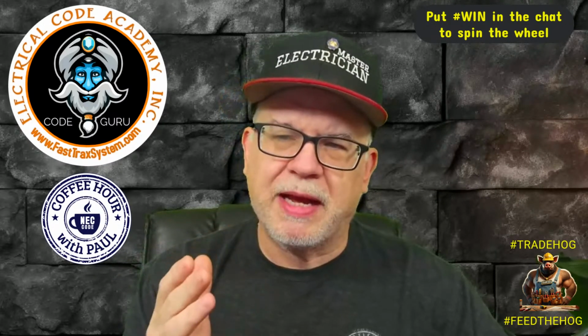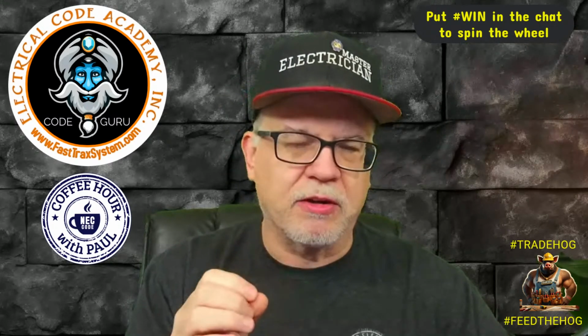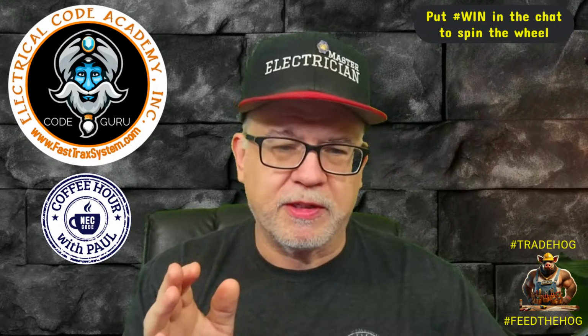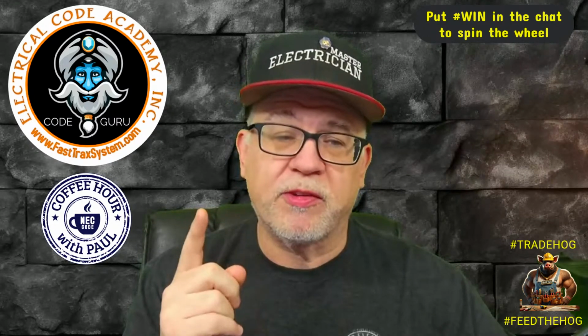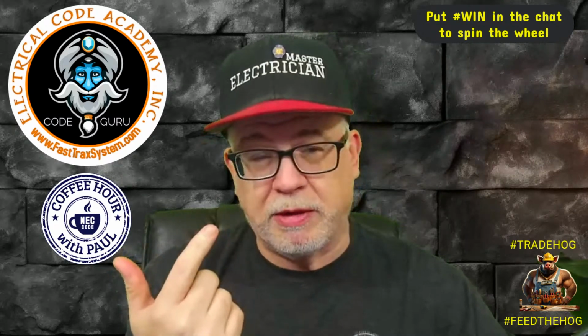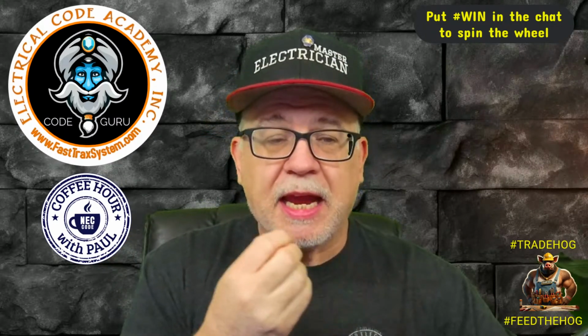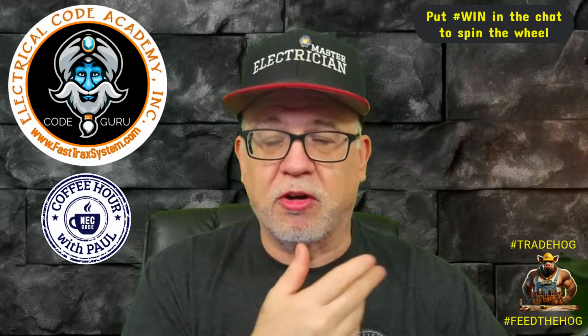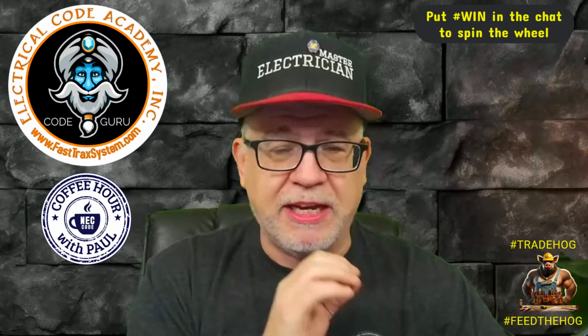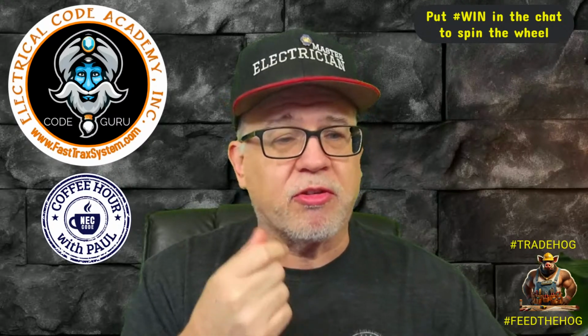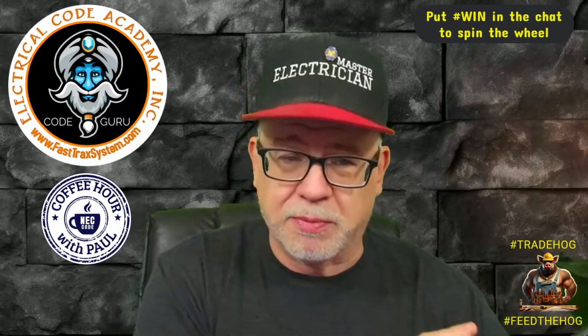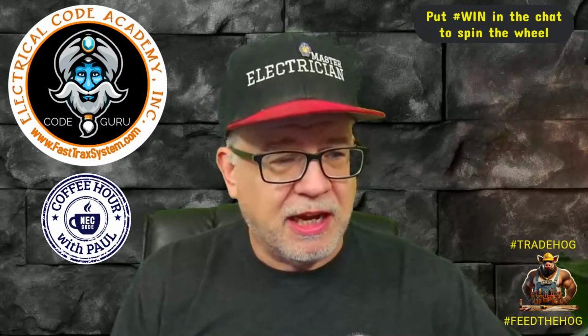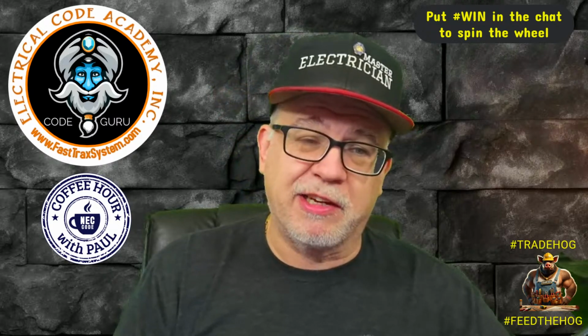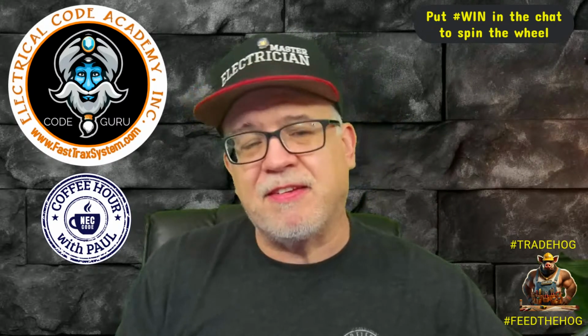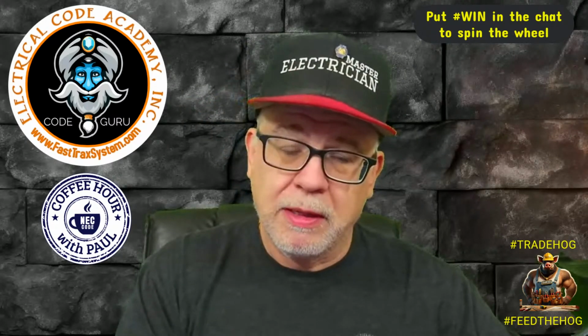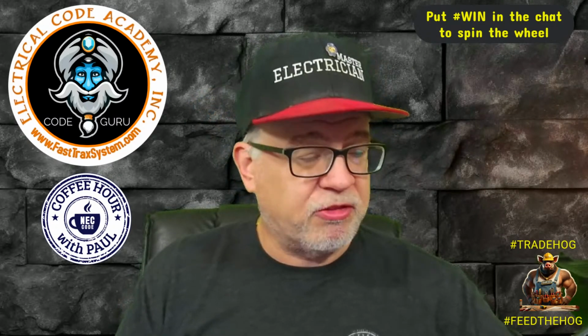So now we're going to talk a little bit about the identification of the wire when it comes to equipment grounding conductors. A very important conductor serves two main functions. One, facilitate the operation of an overcurrent protective device. That's the equipment ground. It helps clear the breaker on a ground fault. And then it also establishes a reference to earth. It ties everything together, so it serves a bonding function. Now, the definition of equipment grounding conductor also has an informational note that reminds you that it serves multiple functions. There's a faction of people out there that would like to see the equipment grounding conductor changed to equipment bonding conductor. But it's unnecessary, because it serves a grounding role, but it also serves a bonding role. And so it makes it clear.